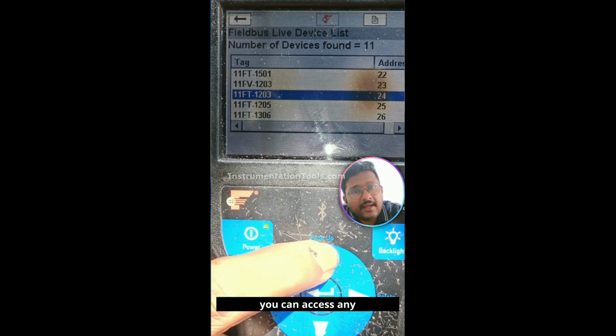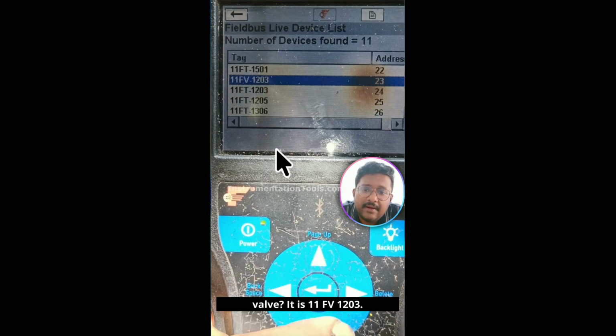Remember, you can access any device from this list. You can enter and view all the configurations. You can see diagnostic messages, or you can do the calibration of any instrument by connecting to any instrument on a Foundation Fieldbus segment. What is the tag name of my control valve? It is 11FV1203. The device address is 23.